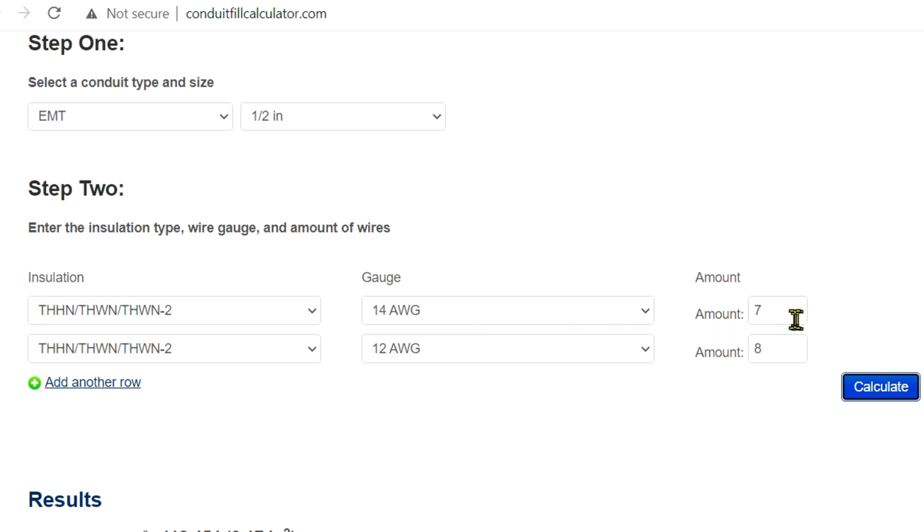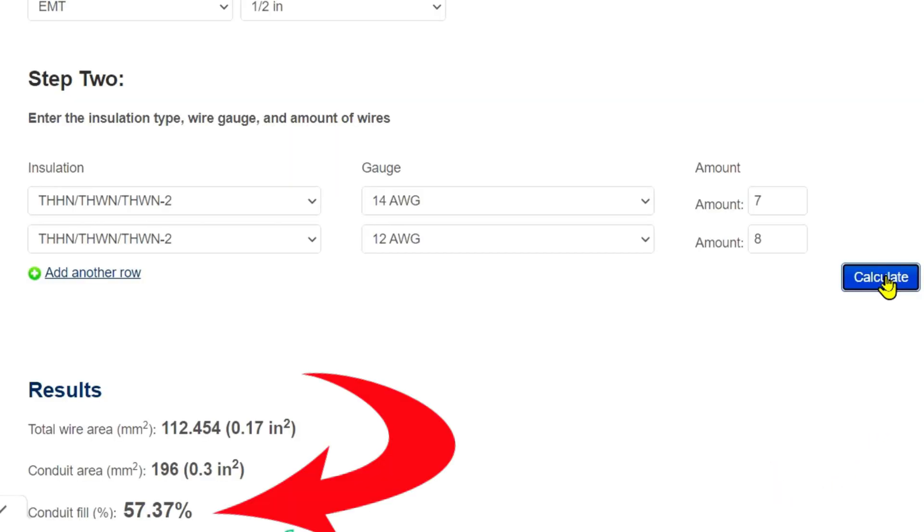So we've got seven 14-gauge THHN and we have eight 12-gauge THHN. We have this all filled out, EMT half-inch, and there it is: 57.37% fill.